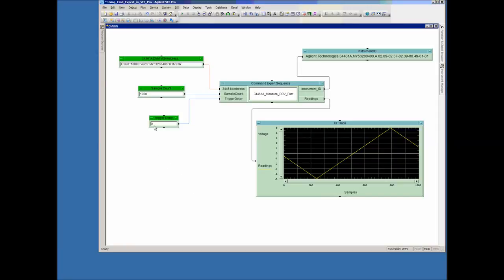We can also put in a trigger delay. This is a delay that can happen before the first measurement and in between measurements. I'll put in a one millisecond trigger delay and rerun this. You should see it slow down and capture about two cycles of the waveform or a little more—and it does.